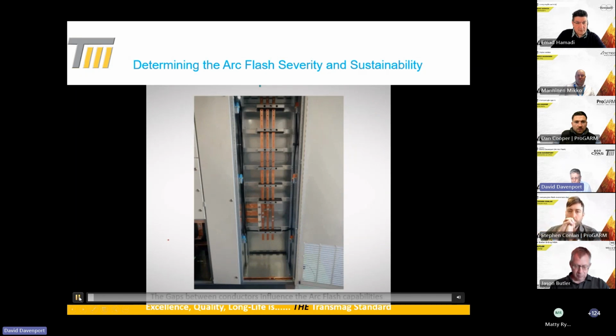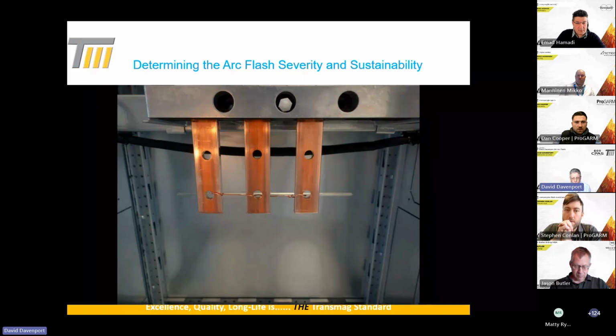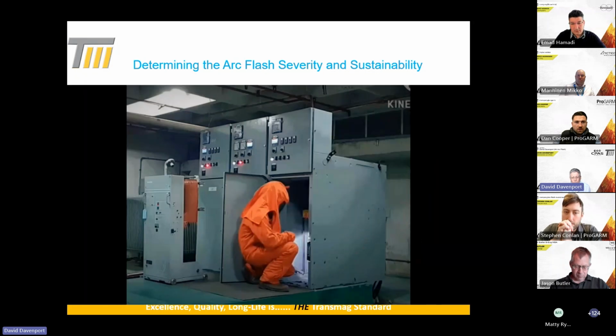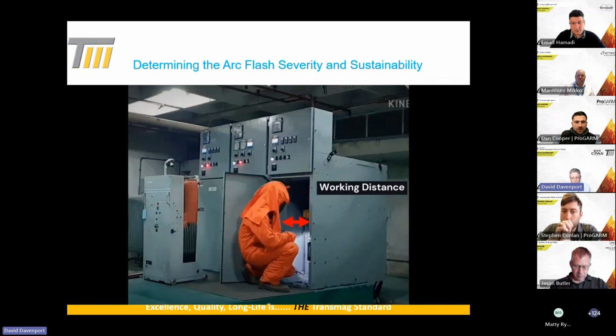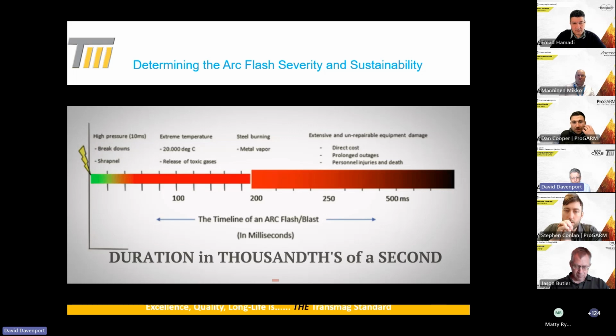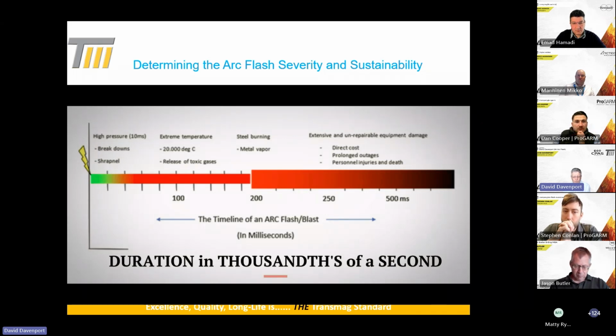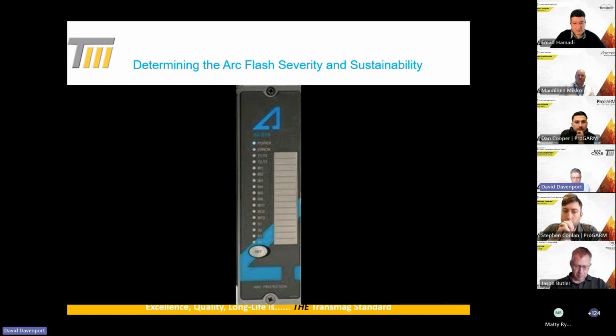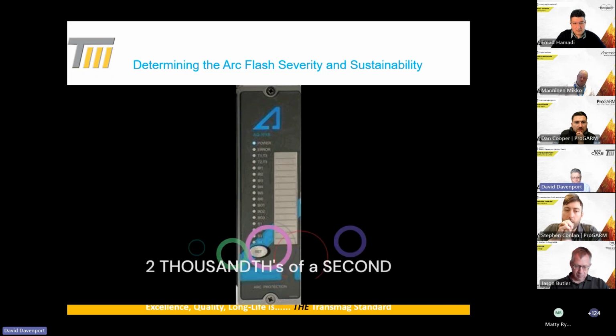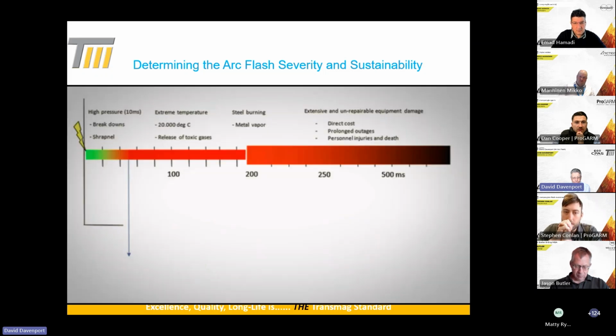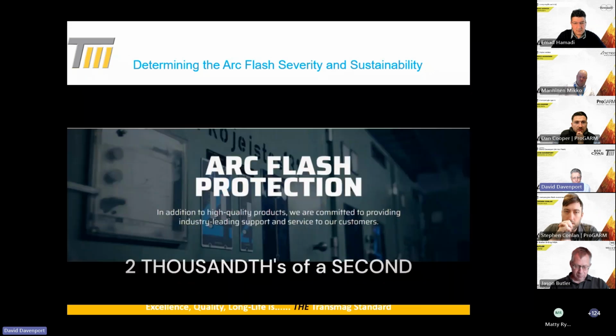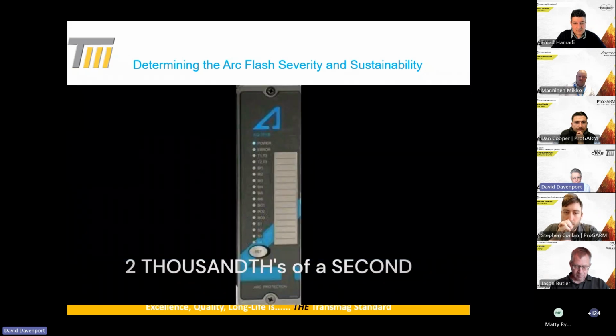So, what are our options? The contact gap can only be affected at the time of design, so we can do nothing further with regards to that existing gap. The distances will be whatever the distance required to carry out the task, so we cannot affect that. However, the duration, which is the most critical element, is what we can and will drastically reduce with an ArcTech arc flash relay. The quickest responding relay on the planet, taking just 0.002 of a second to send that trip signal at the onset of an arc. So, how does this incredible device operate?